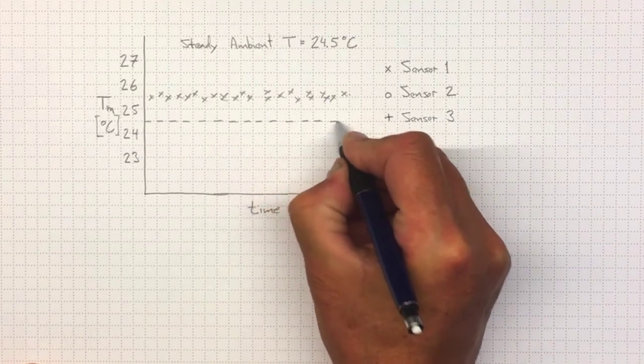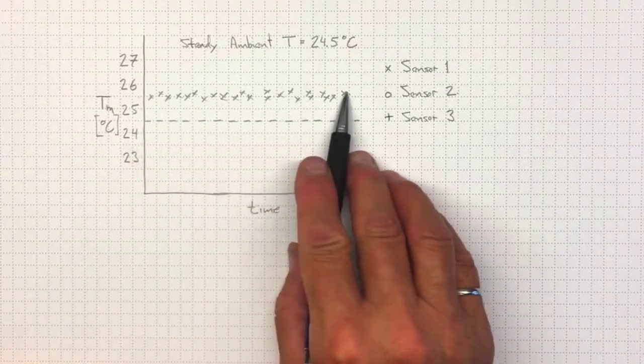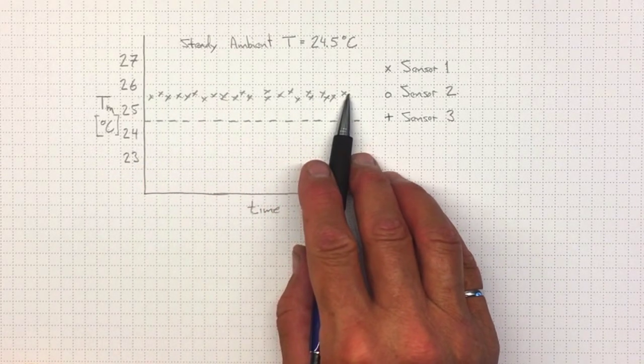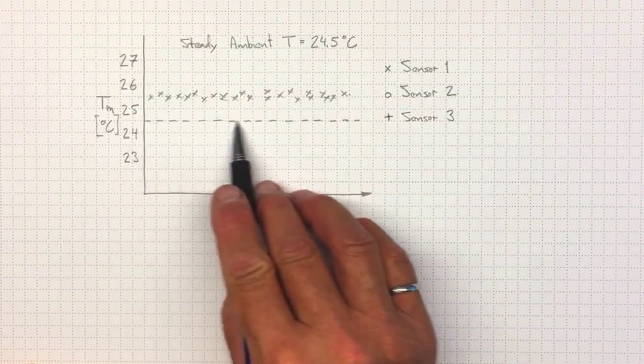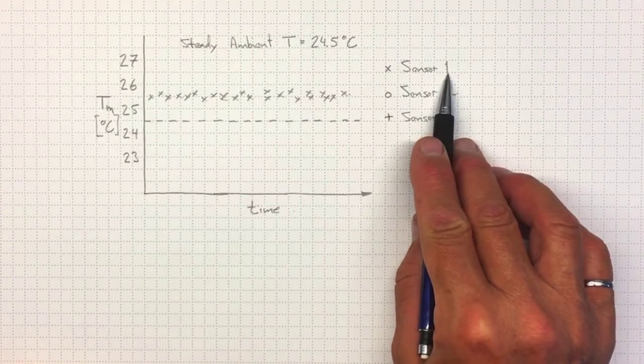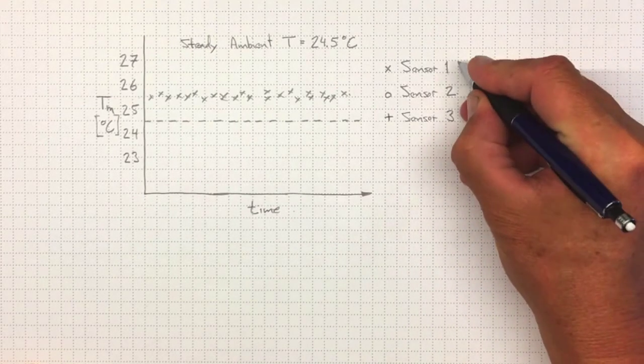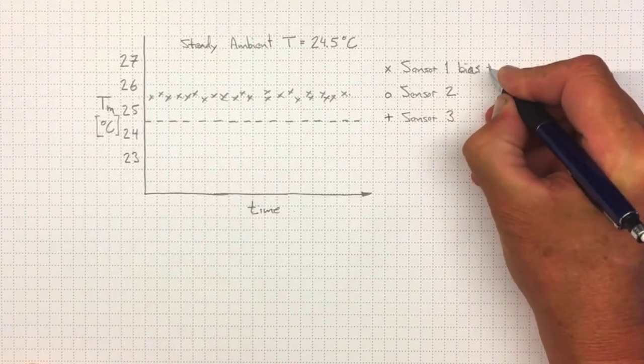Now, if I made this measurement, I could correct that knowing that it's off by one degree. I could take all of the results and reduce them by one degree and wind up sitting pretty close right on that line. That is, if I actually calibrated sensor one and knew that it had a bias of plus one.